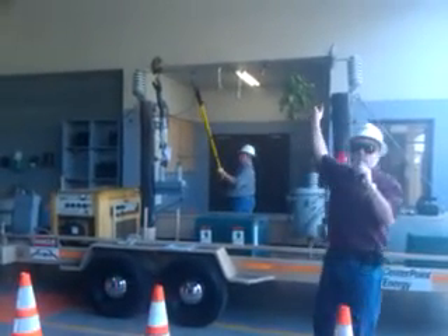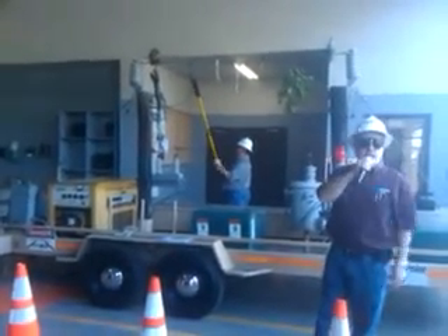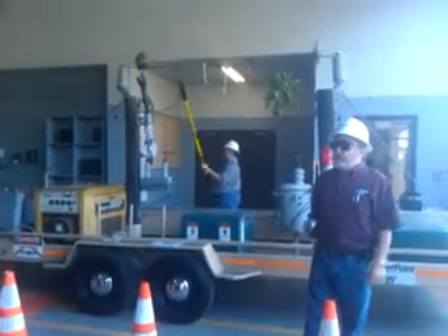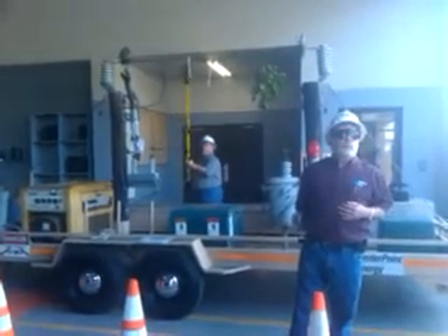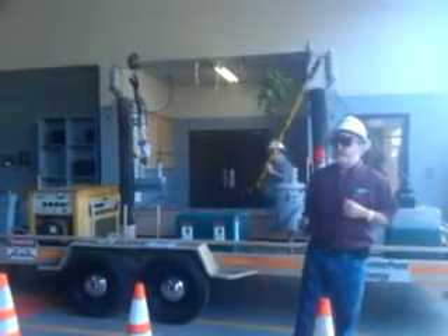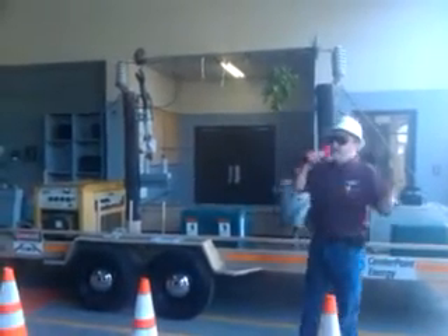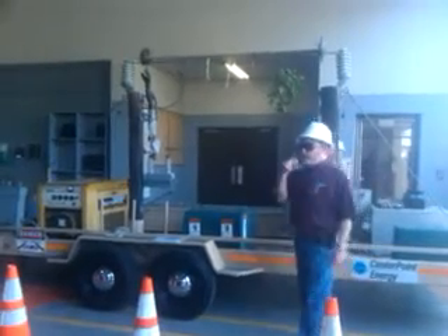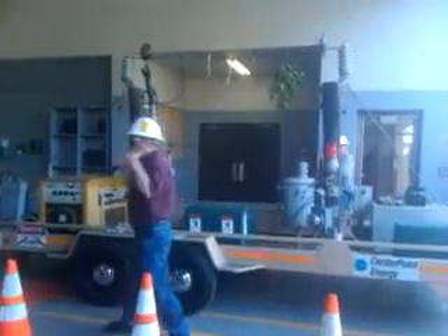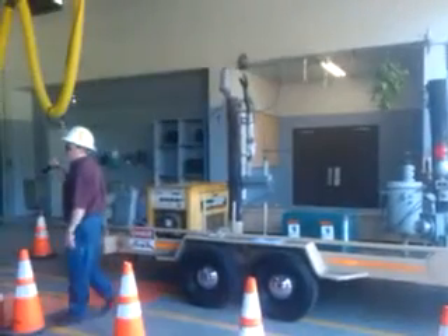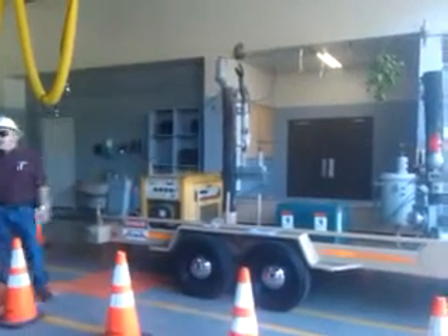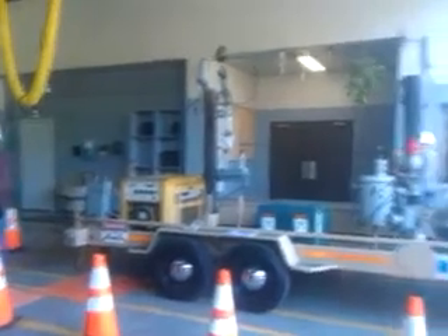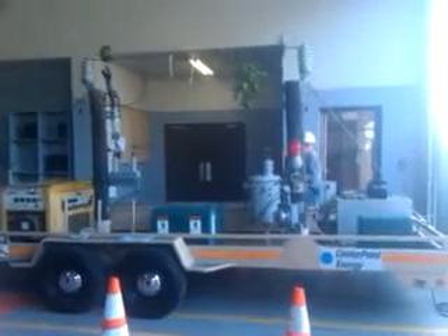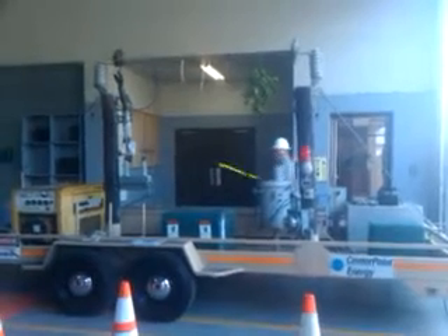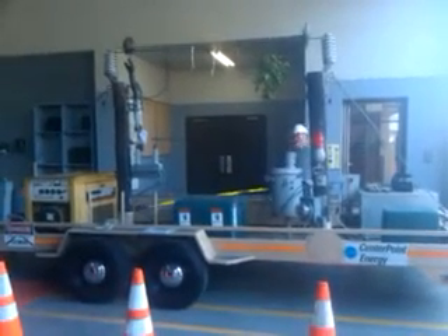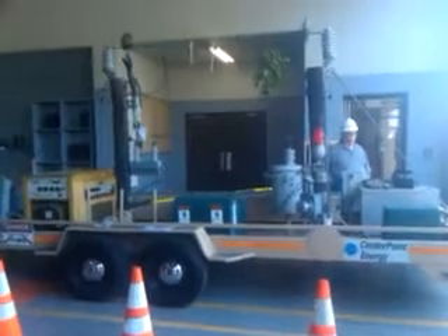How come the bird can sit on that wire up there and never get hurt? It's going to be 7,200 volts. It's not grounded, it's at the same voltage as the wire. And if it's at the same voltage, current doesn't flow, right? You have to have a difference in potential, a difference in voltage. So that bird up there on the wire, that'd be just like you in a car. You could sit in the car all day. You'd be at 19,920 volts, but you're not going to get hurt unless you make a path to the ground. You touch the vehicle and the ground at the same time, you're in trouble. It'd be the same with that bird. If that bird could reach its feet all the way down to the ground, it would be in trouble. As long as it stays on that wire, it's fine.